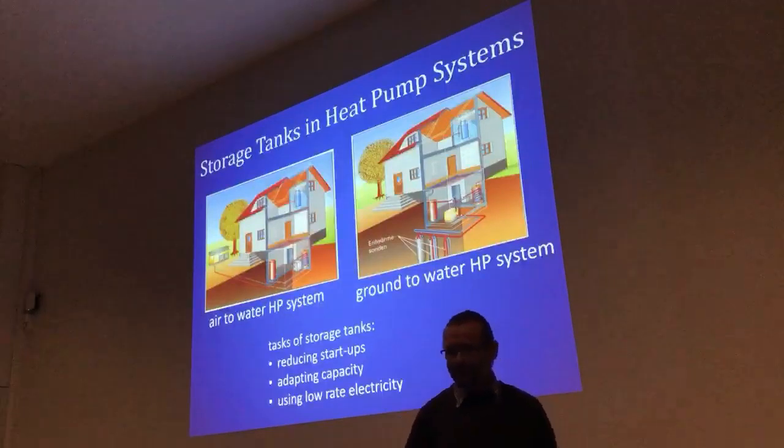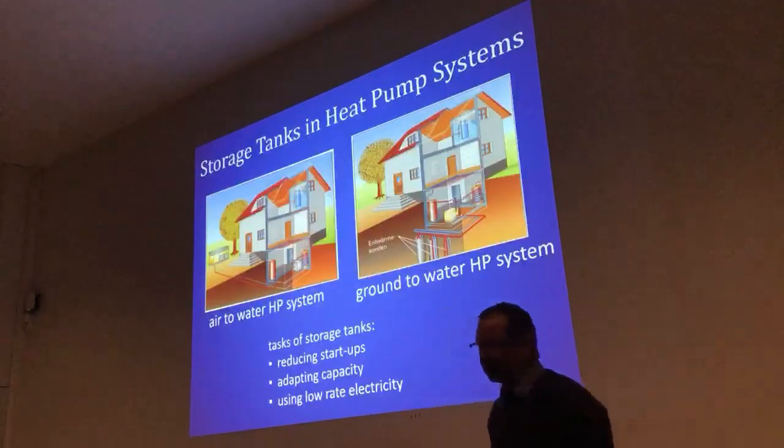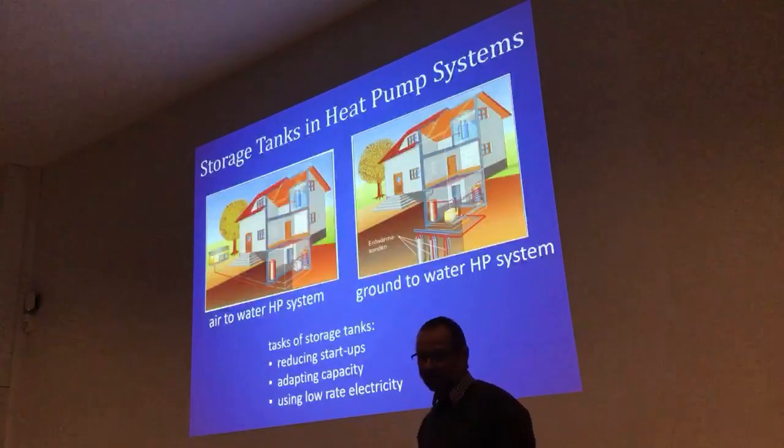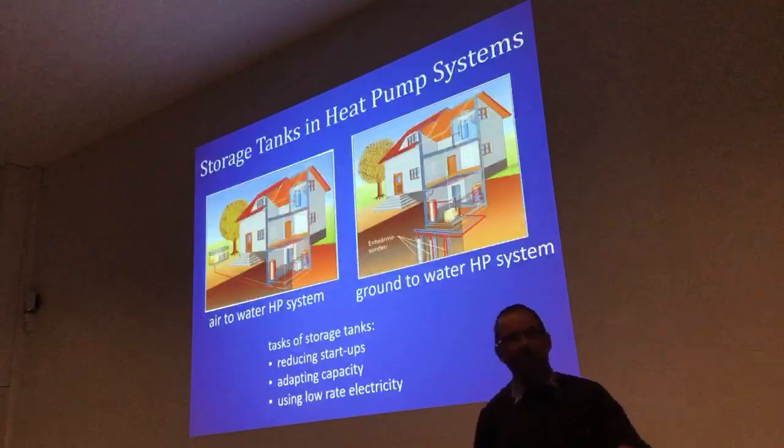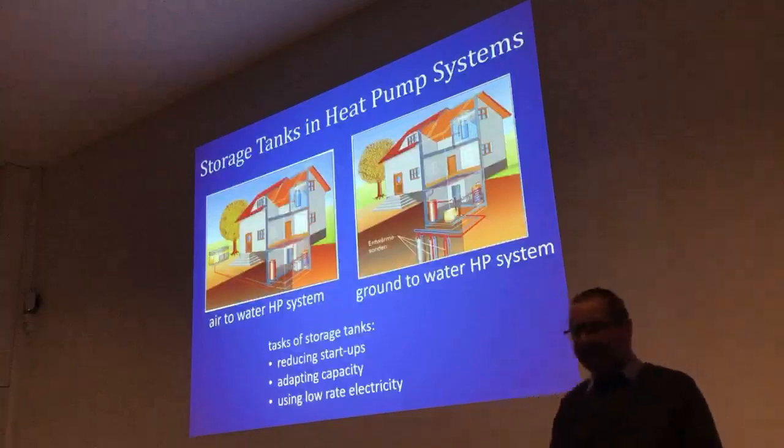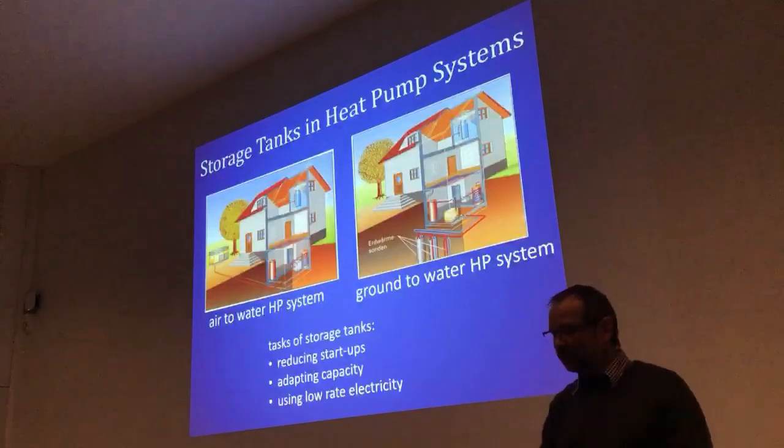This storage tank is used to reduce the start-up of the compressor of the heat pump and to adapt the heat capacity of the heat pump to the heat demand of the building. In the future, these storage tanks may also be used to exploit low-rate electricity.